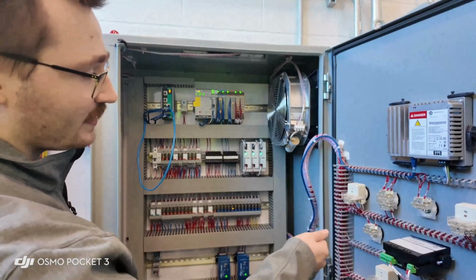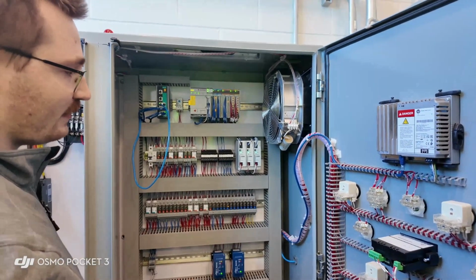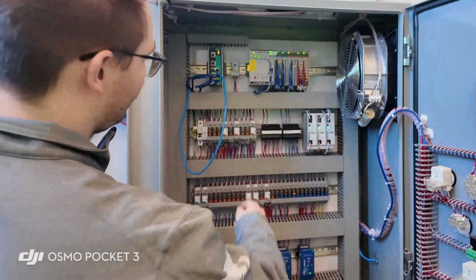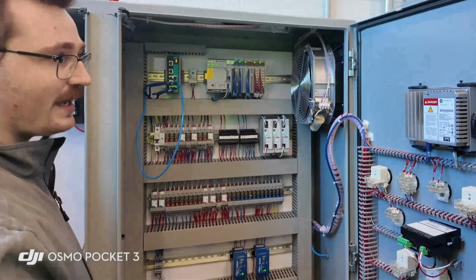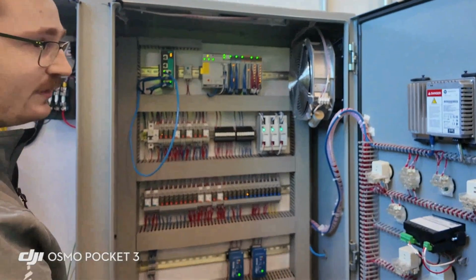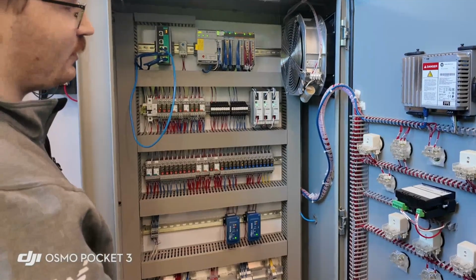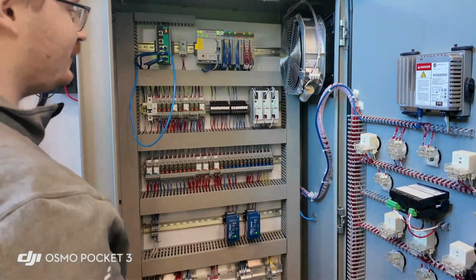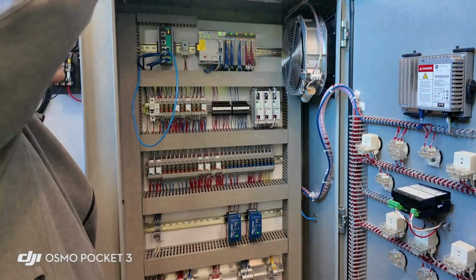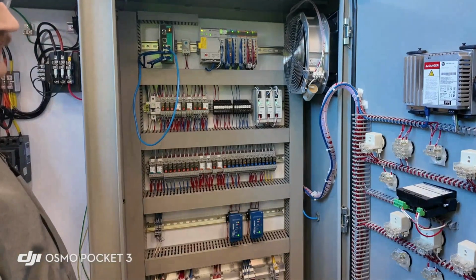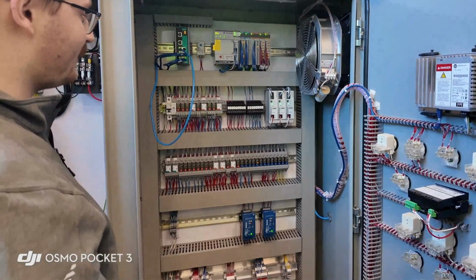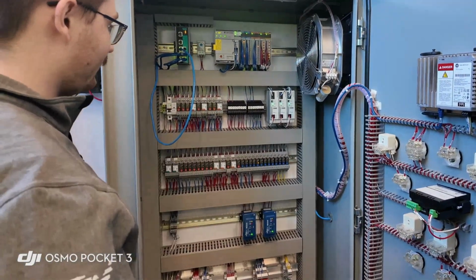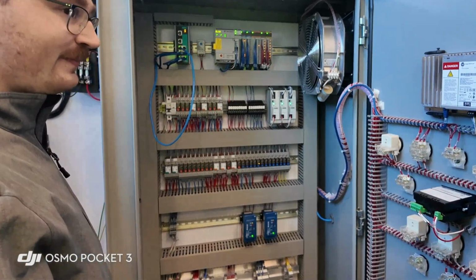So you have to manually reset it. Now, on the next operation, it's not going to look for the level transducer. It's going to hit level set point 1 and run it back up. If it keeps filling up, it's going to hit level set point 2, and it's going to keep doing that. It's more or less so, if the transducer does fail, you don't want it filling up to the high level every single time and then starting both pumps. It acts as a barrier, so you're not constantly running both pumps in backup.